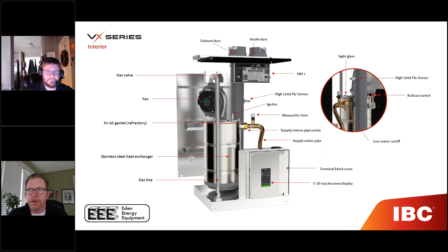Perfect. And then obviously the low water cutoff. As Mike mentioned, that's our standard low water cutoff. That being said, if your jurisdiction does require an external safety, say you need a flow switch for smaller boilers or an external low water cutoff, we can wire those directly into the boiler as a good option. That's what those two blue jumpers on the inside are. We have the ability to wire up two of them to prove there, so it's good for meeting all your code requirements.